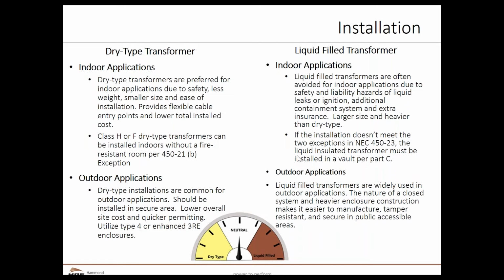And we don't need a fire resistant room. So a general room construction for an electric room, for instance, is more than adequate for a dry type transformer. Now, when we install a dry type transformer outside, there are a couple of concerns that we have. We would like to have that unit installed in an area that's secure from the general public, because there are probably vent holes and stuff like that within the transformer.